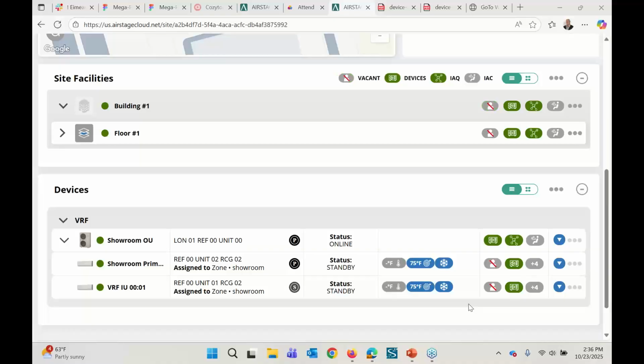There was another question about a BMS. No, AIRSTAGE Cloud is not going to connect to a building management system. If you're going onto a job site that already has a BMS, you'll use the NTSys box we sell to create a BACnet gateway. That gateway allows the BMS to handle set points and schedules. With that said, we do have a lot of large customers who already have a BMS system.